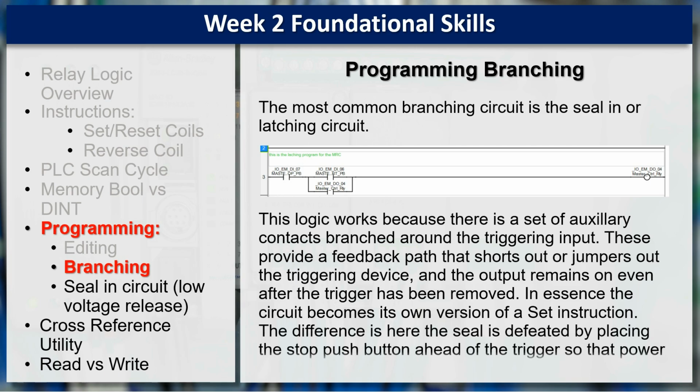In essence, the circuit becomes its own version of the set instruction. The difference here is the seal is defeated by placing the stop push button ahead of the trigger so that power is removed once the stop is pressed, therefore breaking the seal.